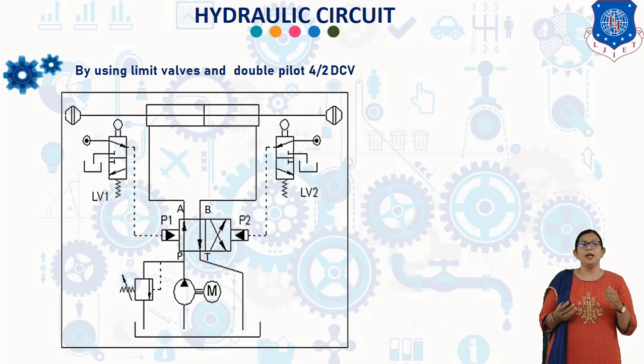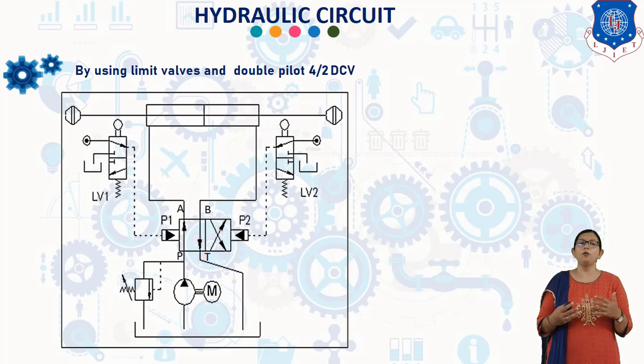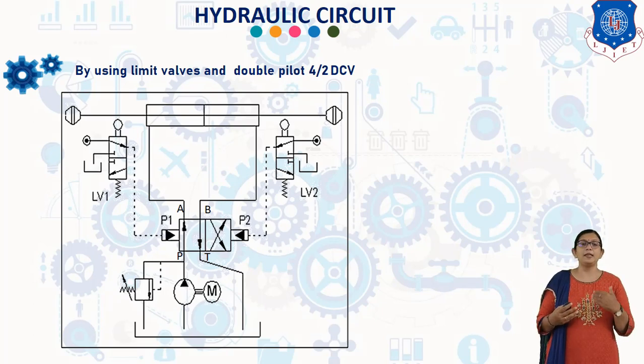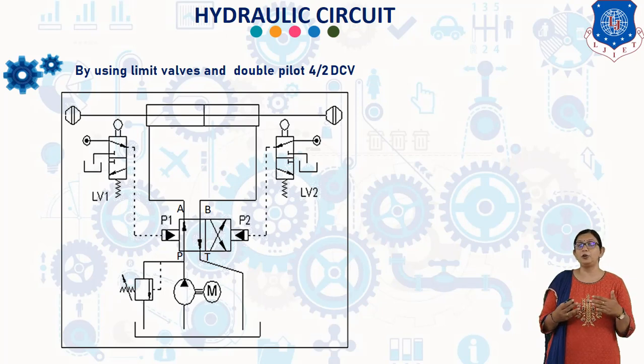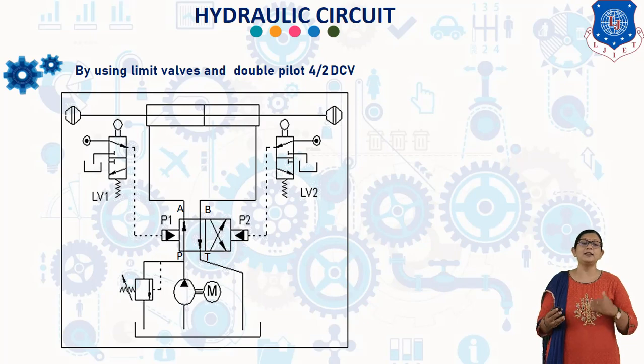In the second position of the 4/2 DCV, oil under pressure flows from P to B and A to T. Hence, the cylinder retracts. By the end of retraction, the cam presses limit valve LV2, and oil under pressure flows to pilot P2. This shifts the spool of the directional control valve back to the first position and the cycle is continued.